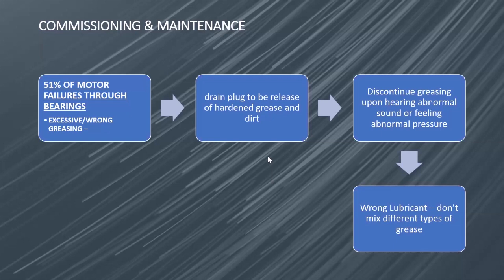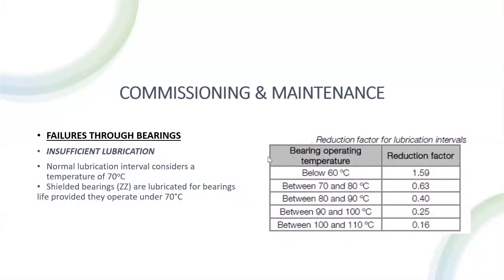Wrong lubricant has been found to contribute a lot to motor bearing failure. Check the motor technical data and see the grease which was used. Whenever two greases are mixed, it causes overheating. So if it's an EP2 grease, you get your EP2 grease. Don't mix EP2 with EP3 grease. Chances are that you cause a motor failure, and this has been observed to contribute a lot to motor bearing failure, which contributes 51% of motor failures.